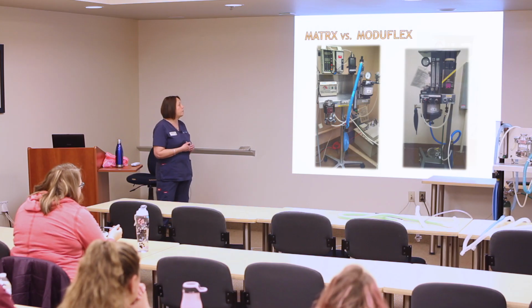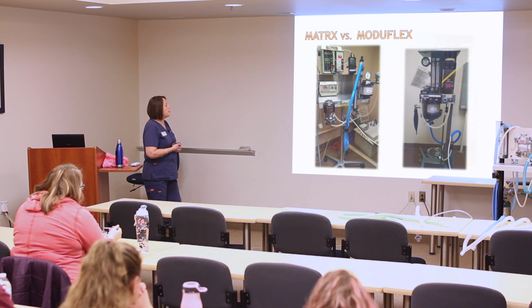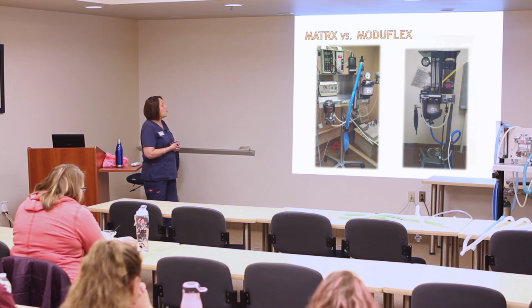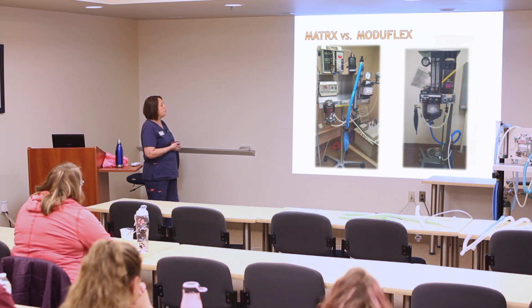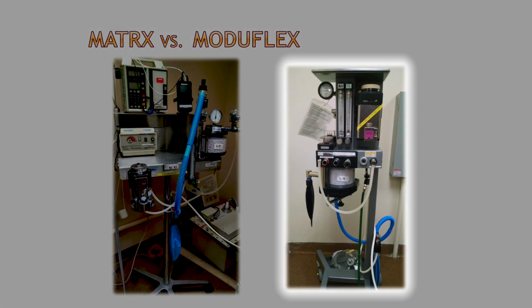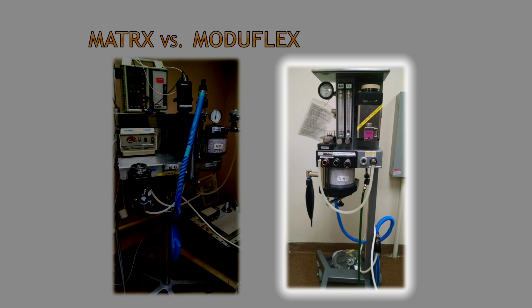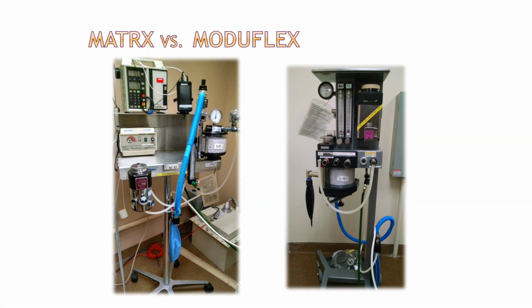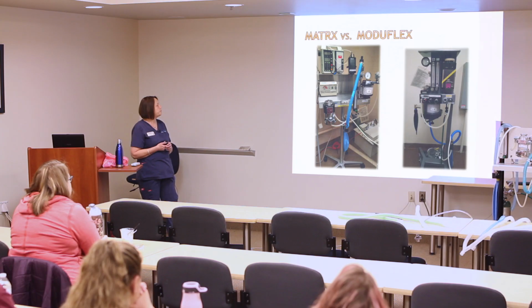Also, when carbon dioxide percolates through the soda sorb canisters on most of these machines, it percolates from the bottom to the top. The DRE is the one that actually percolates from the top down, and gets a majority of its color change on top—that's probably one of the bigger differences in the flow of gas through that machine.